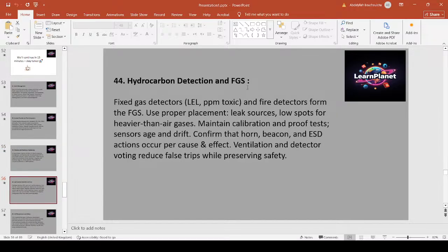Hydrocarbon detection and FGS. Fixed gas detectors, LEL, ppm toxic, and fire detectors form the FGS. Use proper placement, leak sources, low spots for heavier than air gases. Maintain calibration and proof tests; sensors age and drift. Confirm that horn, beacon, and ESD actions occur per cause and effect. Ventilation and detector voting reduce false trips while preserving safety.